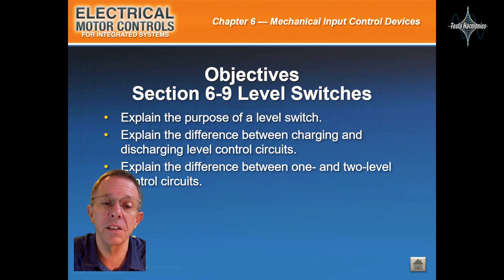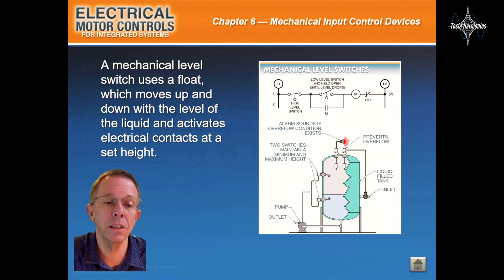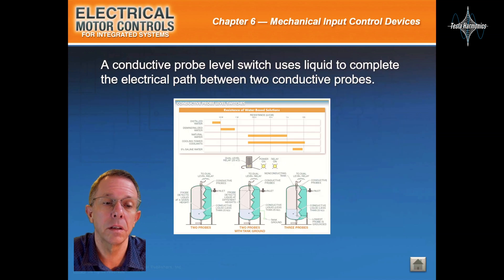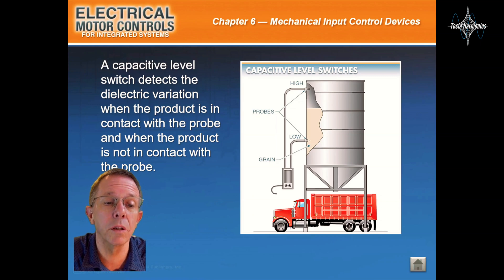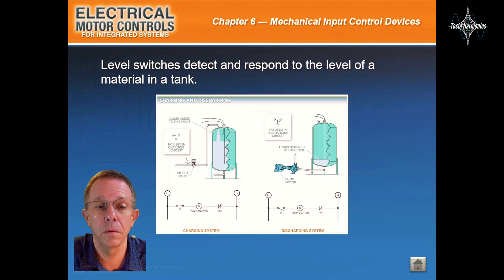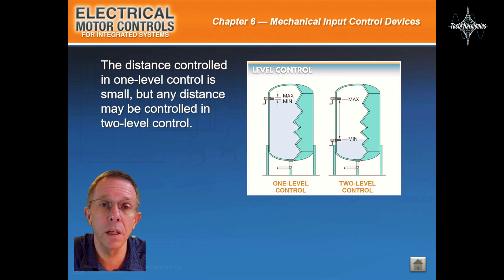Section 6-9: Level Switches. A mechanical level switch uses a float which moves up and down with the level of a liquid and activates electrical contacts at a set height. A conductive probe level switch uses liquid to complete the electrical path between two conductive probes. A capacitive level switch detects the dielectric variation when the product is in contact with the probe and when it is not. Level switches detect and respond to the level of a material in a tank. The distance controlled in one-level control is small, but any distance may be controlled in two-level control.